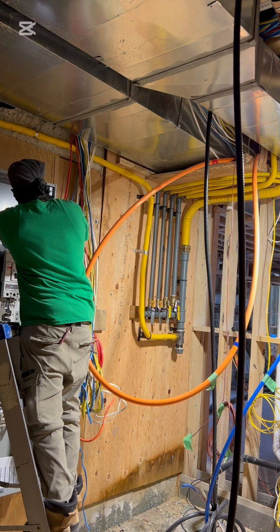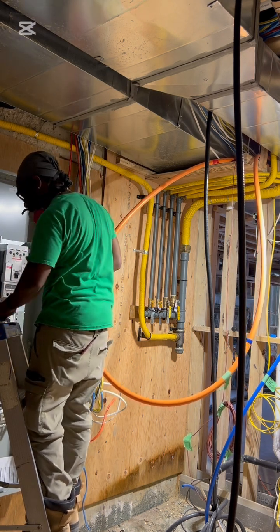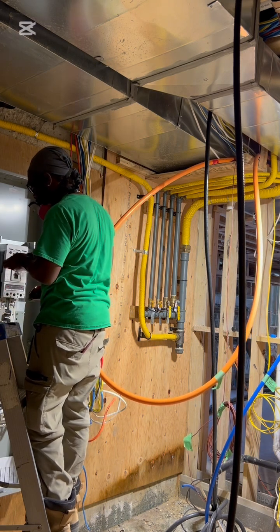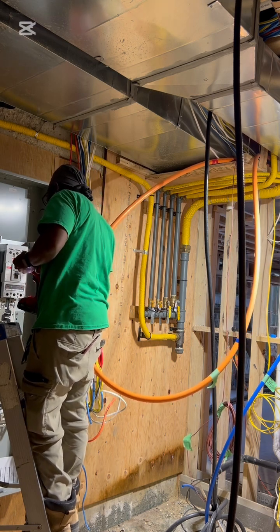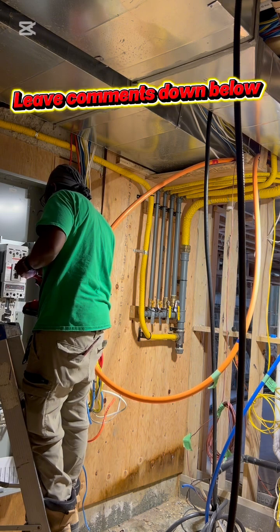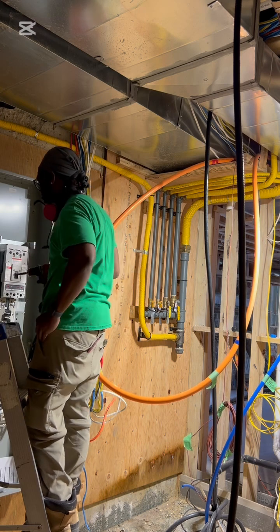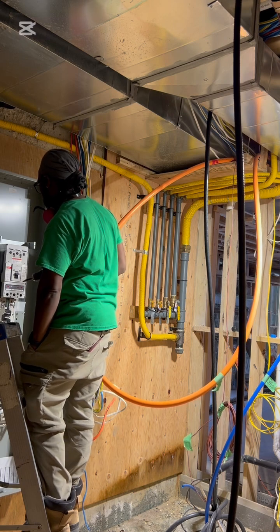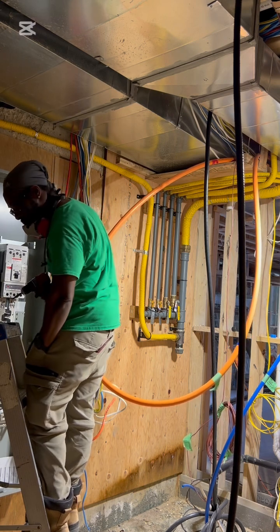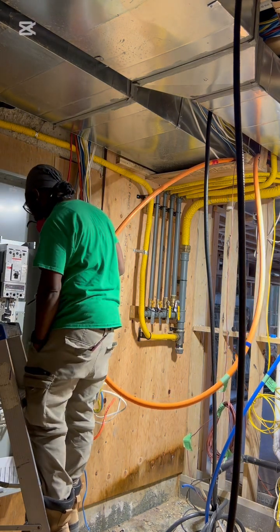What makes it 400 amps? When it's used in large homes, commercial duplexes, the difference from 200 amp or 100 amp is higher load demand and conductor requirements. Voltage: 120 volts slash 240, single phase. 400 amps is not a regular service entrance for residential homes. Normally we use 100 to 200 amps, so this is considered a very large installation.